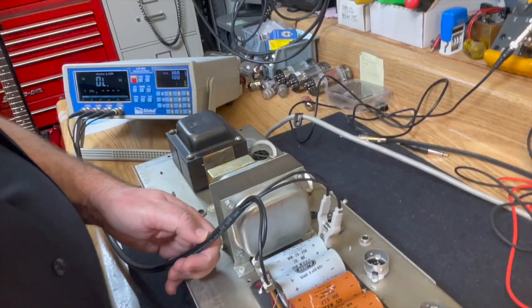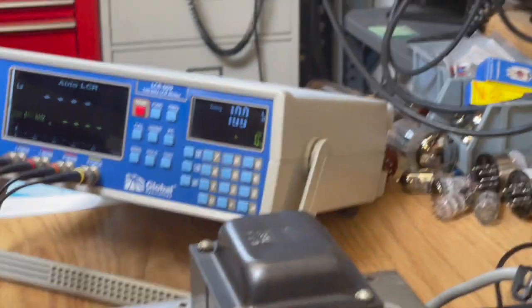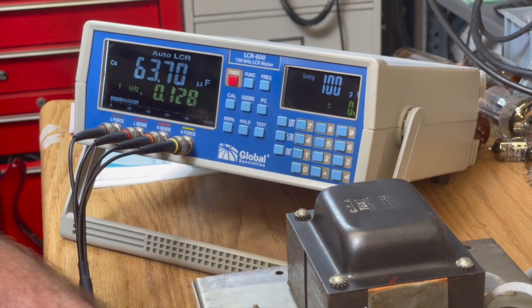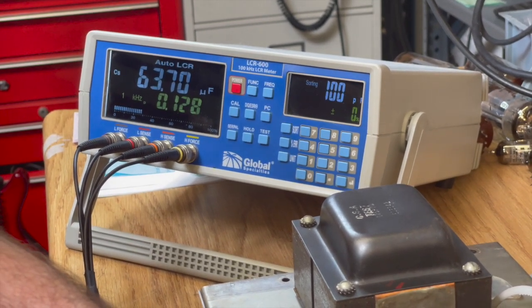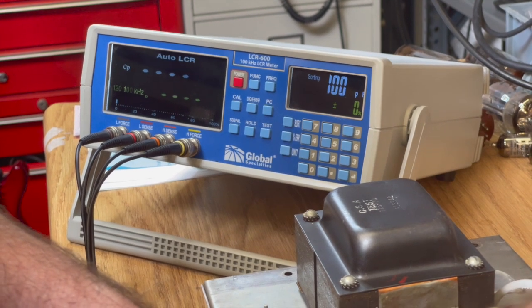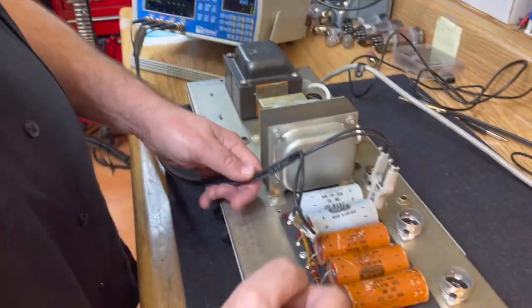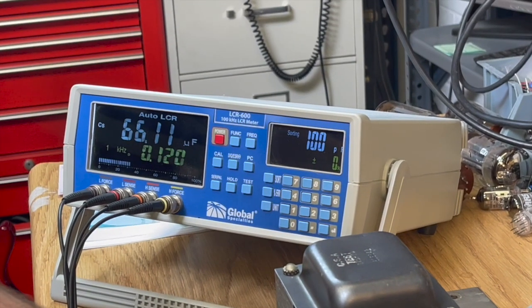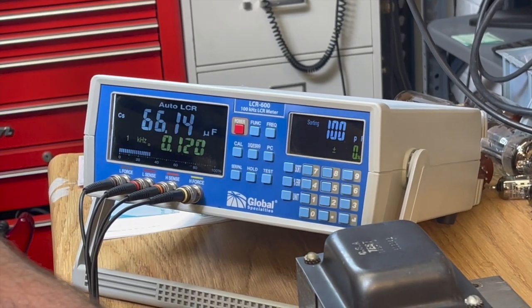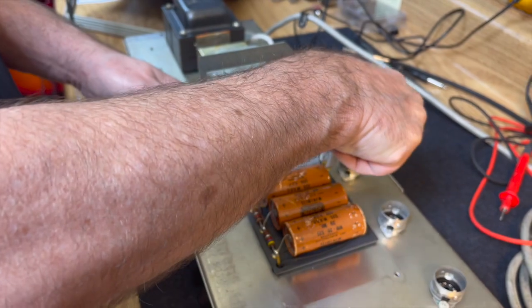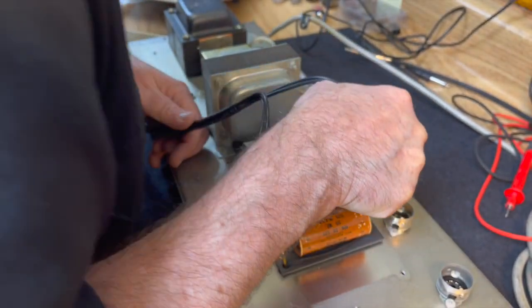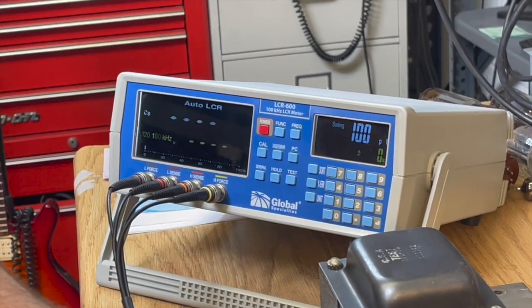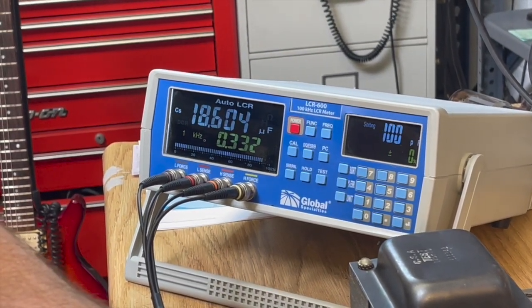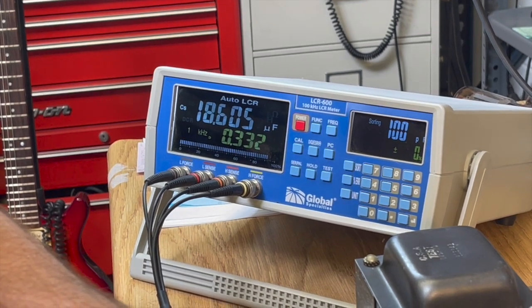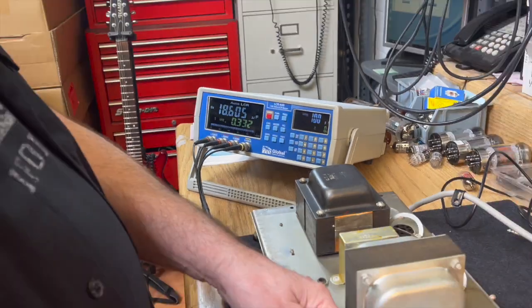Starting here, we were almost dead on where it was supposed to be. 63. That's still great. A little lower, but still well within tolerance. This one, 66. Same deal. A little below the rating, but well within its tolerance. Here we've got 18.6. And again, this is a 20 mic capacitor, so that's great.